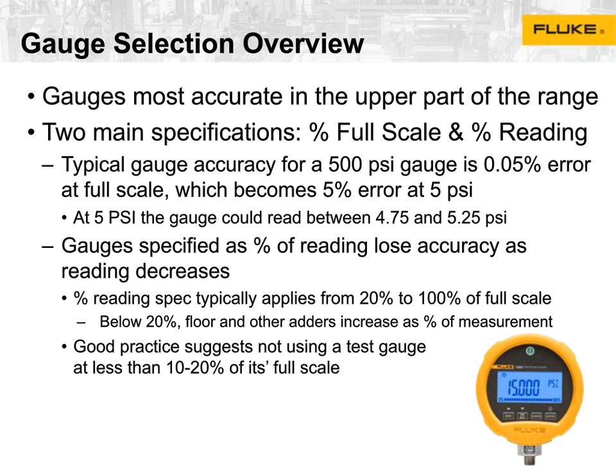One of the reasons manufacturers have gone to percent readings is that it allows you to sort of ignore some of these issues at the lower end. The problem is that at the end of the day, the sensors simply become less accurate the further away you get from the maximum end of the range. So most manufacturers who specify as percent reading will set a floor spec somewhere between 0 and 20%, and it basically says even if you have a lower reading than this, your total error will be fairly high. Good practice suggests that if you're using a gauge at less than 20% of its full scale, it's probably not the right thing. You probably need to go get another gauge.